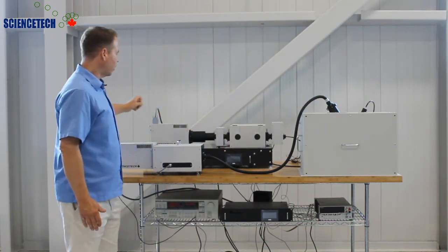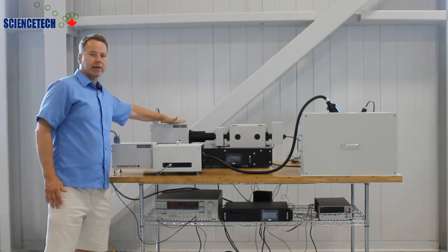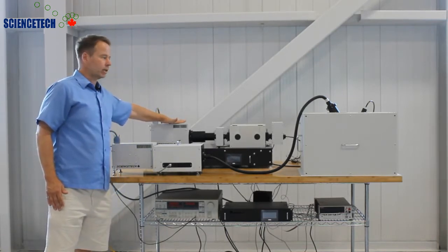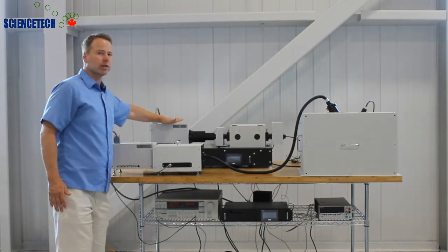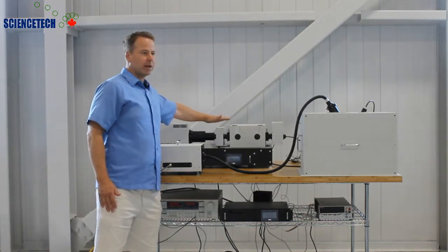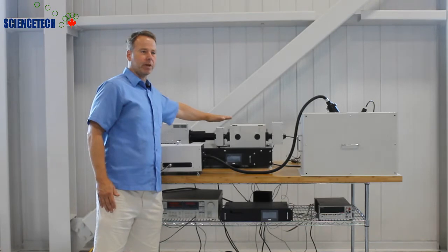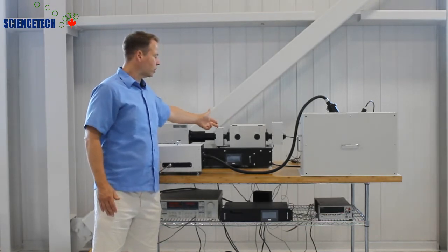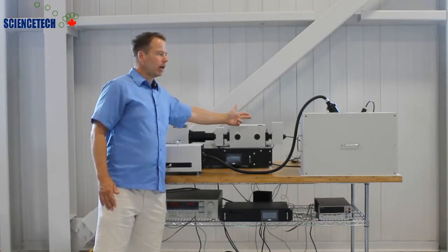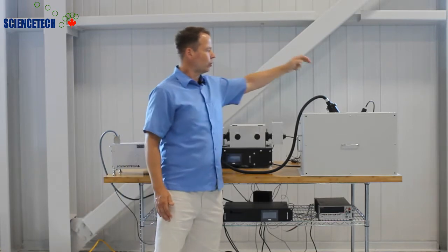The heart of the PTS is the TLS, which is our tunable light source. This is a xenon light source and a monochromator that makes a quasi-monochromatic beam. It also has an order sorting filter and a chopper, and this needs to be directed towards the sample.